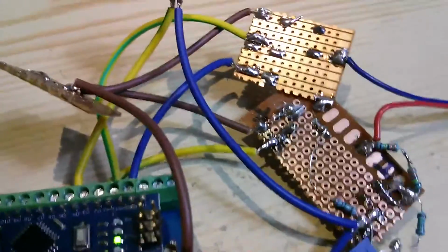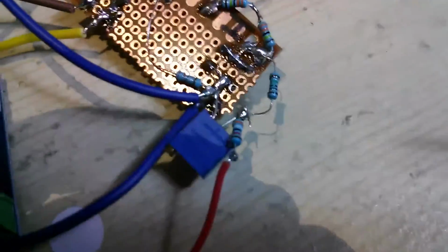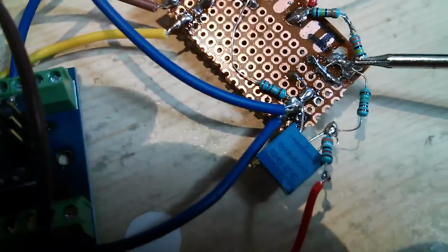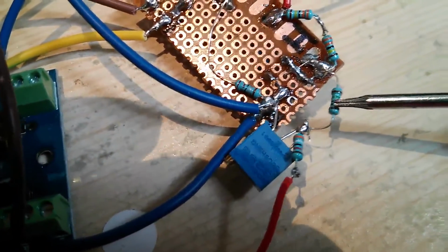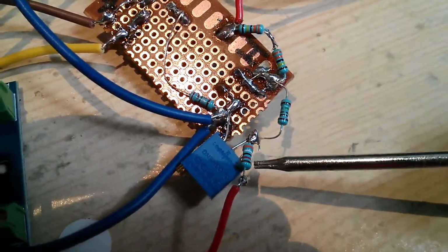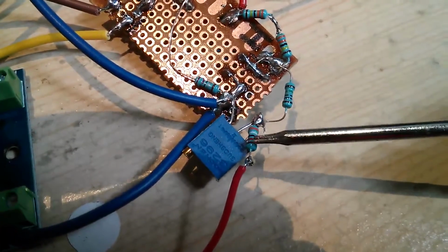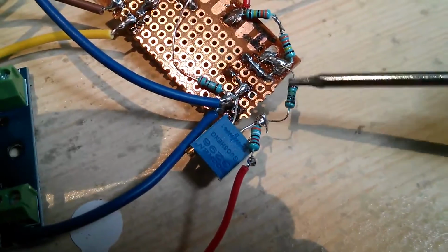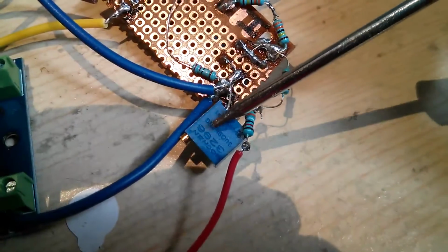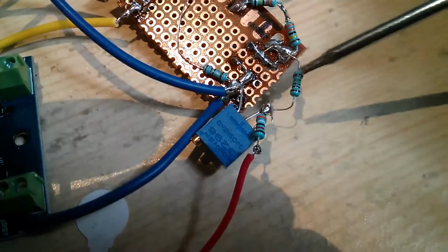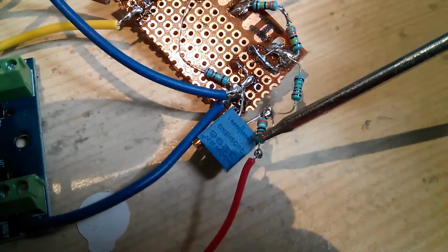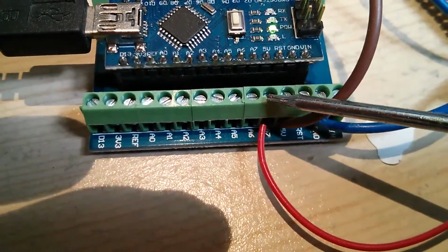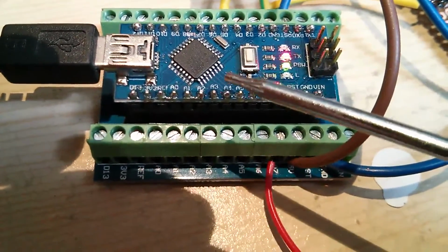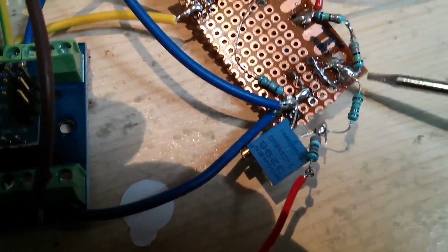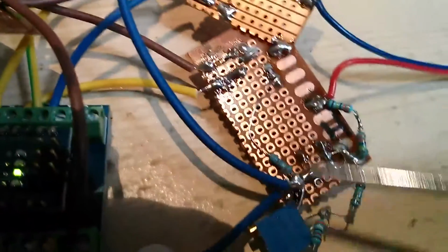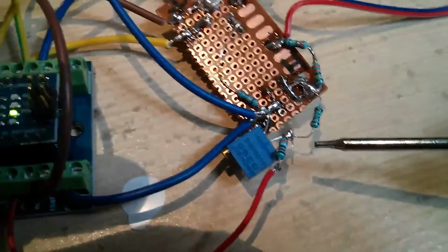So this voltage divider, I need a pointing stick. Let's find a pointing stick. This voltage divider takes the 400 volts from there, divides it down through a 10 megohm resistor, and I think that's a 39k resistor. That one's not used as a divider. Let's try that again. So we've got a 10 megohm, and this preset, this adjuster is set to 50k. So I get approximately a 200 to divide through this chain, and then I've got a high impedance resistor here feeding off to one of the analog inputs on the chip. That analog input reads through the software the voltage that's being fed to the tube. It's not 100% accurate because of losses and impedances and things, because these power supplies are very high impedance out, but it gives a very good indication as to the voltage that's going off.